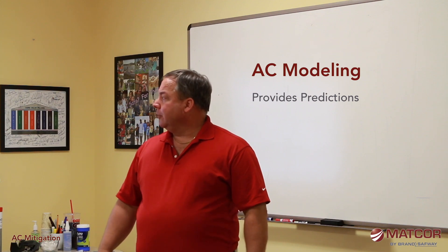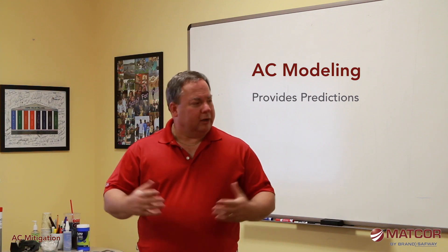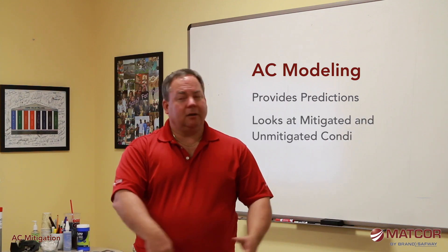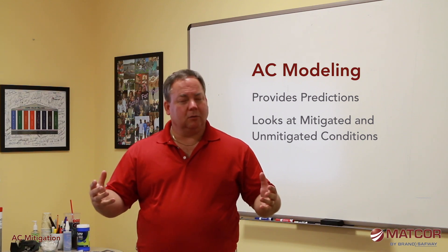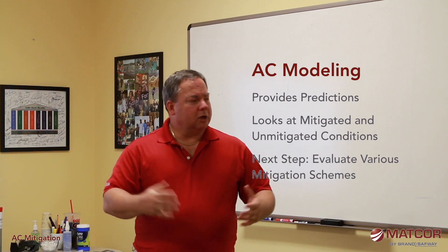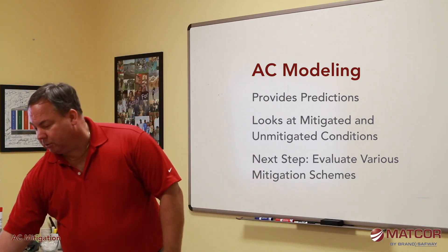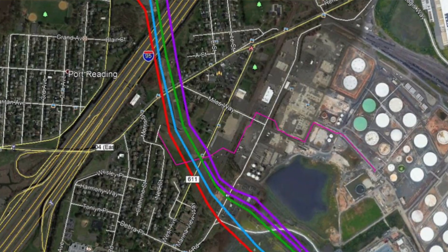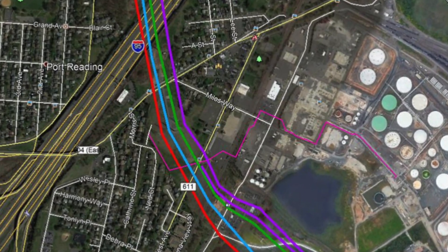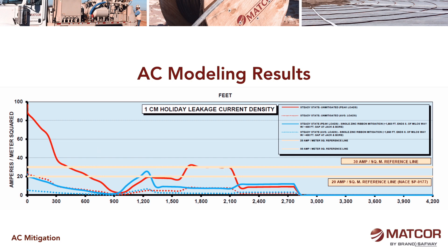We use AC modeling to provide predictions and look at what the mitigated and unmitigated conditions are. We build a model — or alternatively go in ad hoc — and come up with some scheme to mitigate. Going back to this pipeline application we looked at earlier when discussing modeling: the modeling results showed a couple of areas where the red line falls above the 20 amps per square meter lower yellow level, so there are a couple of spots we're concerned about.